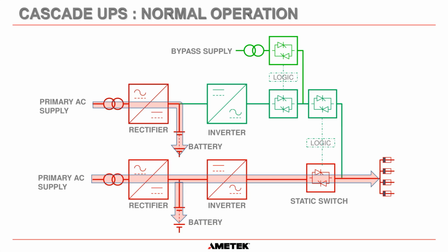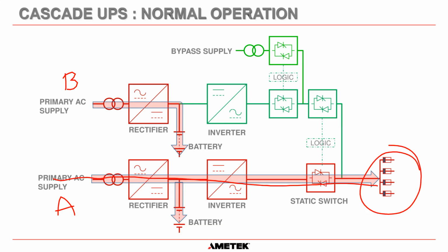And then another topology that we see very frequently is what's called a Cascade UPS. And once again, we'll call this UPS B and we'll call this UPS A. So once again, red is normal power flow. So in a Cascade UPS, the primary UPS, which is UPS A, will feed all the power to the critical loads. The B UPS will keep its battery charged. The inverter will be on, but the static switch here is not on. Okay, it's waiting for a signal, because basically what's happening is UPS B is acting as the bypass supply for UPS A.